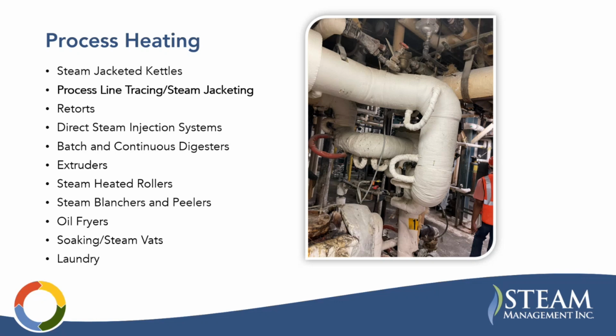This is actually process piping, and this product is being maintained at about 180 degrees. And if you picture underneath this insulation at the end, these two pipes converge so that you have a welding point. So this elbow has a cavity separate from this piping cavity, and that's why you see these little jumpers here. And so for every intersection or every valve, you have to have a jumper so the steam can continue to flow through the system.